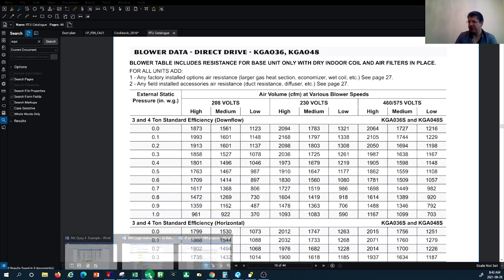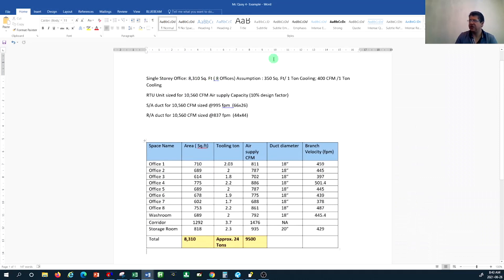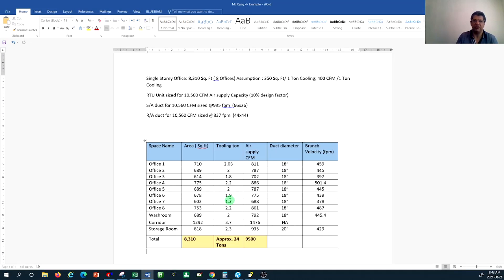From our previous tutorial, we designed for a space of 8,310 square feet with eight offices and some other rooms. We did the rule of thumb calculation to come up with the cooling tonnage of every space, and then based on that we estimated the total air required. I emphasized in the previous tutorials that this is not the formal way of doing this calculation — we need to do the heating and cooling load calculation, whether manually or through relevant software, to achieve the cooling load.